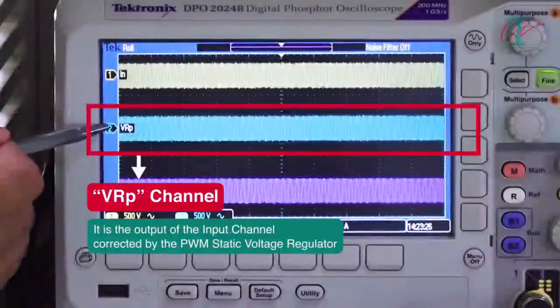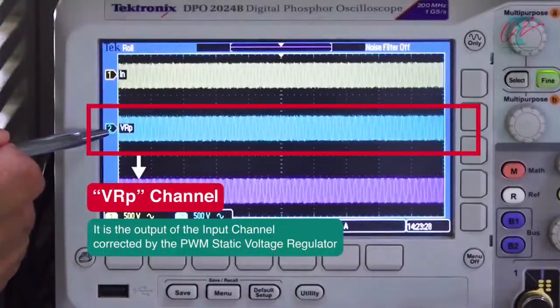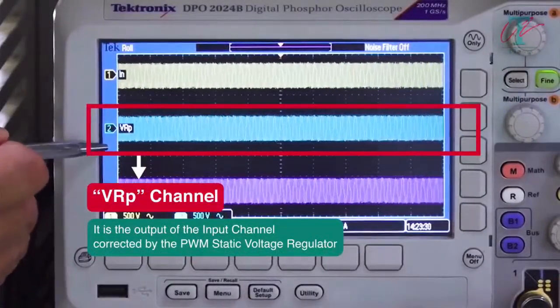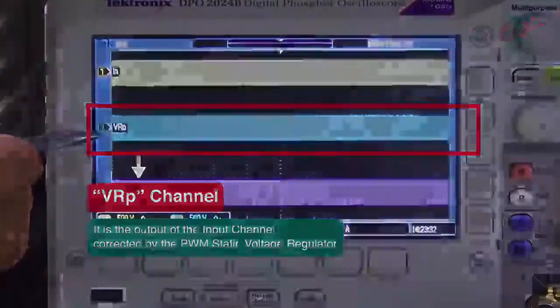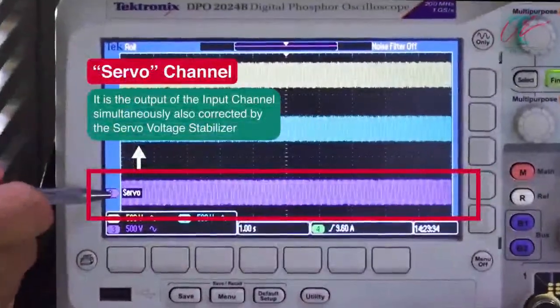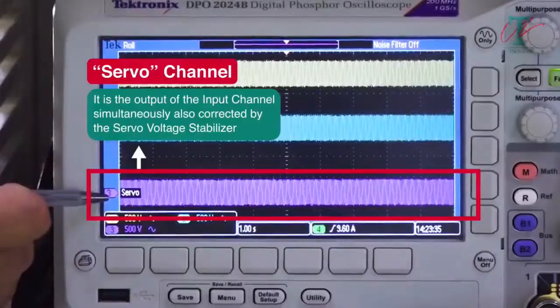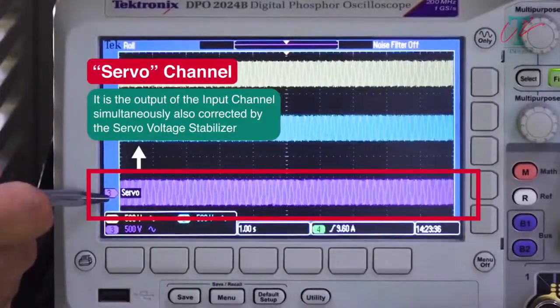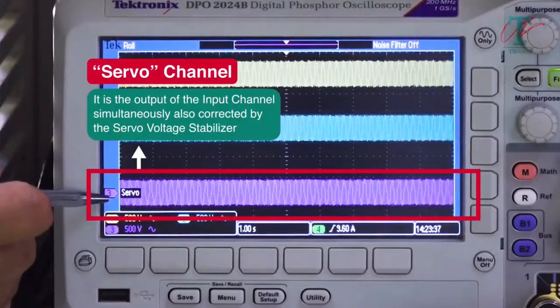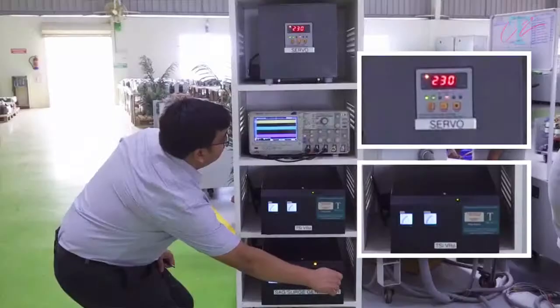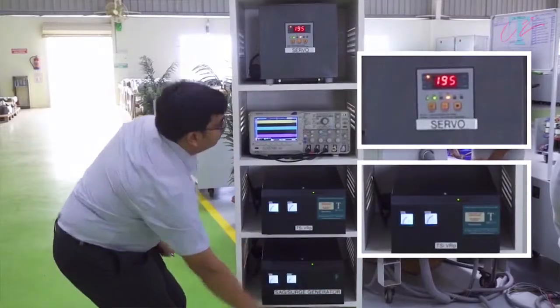This waveform is then corrected by the static voltage regulator, whose output is recorded in this channel marked as VRP. This waveform is simultaneously also corrected by the servo voltage stabilizer, whose output is recorded in this channel marked as servo. We are now ready to observe a sag phenomenon. So, let's generate a short sag.